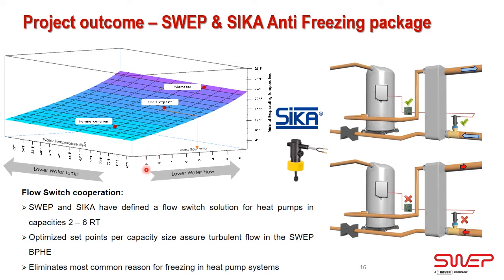And by using this flow switch, number one, you have protection against pump failure, and number two, you know that you're operating inside a very safe envelope of the heat exchanger where freezing is very unlikely to happen.